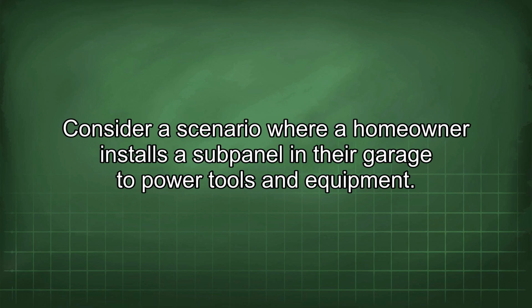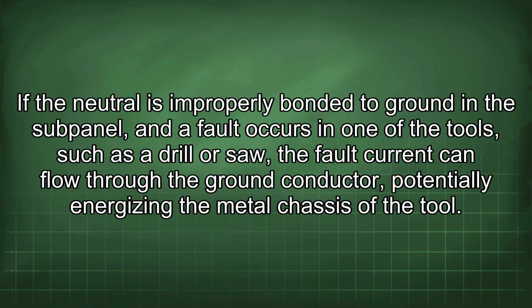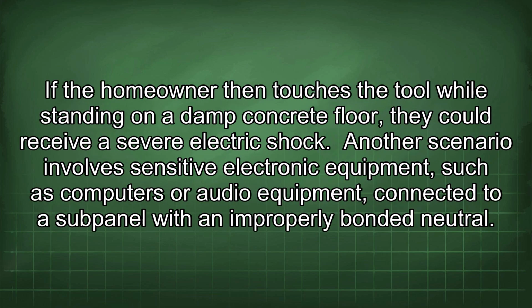Consider a scenario where a homeowner installs a subpanel in their garage to power tools and equipment. If the neutral is improperly bonded to ground in the subpanel and a fault occurs in one of the tools, such as a drill or saw, the fault current can flow through the ground conductor, potentially energizing the metal chassis of the tool.